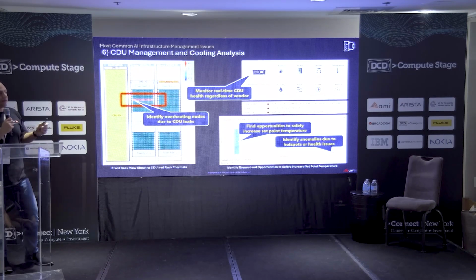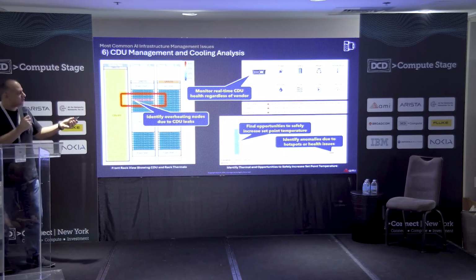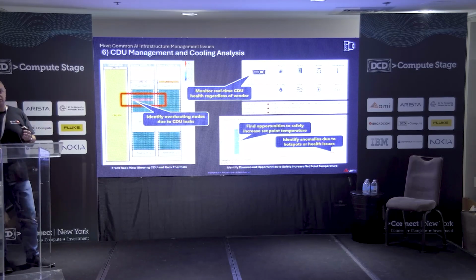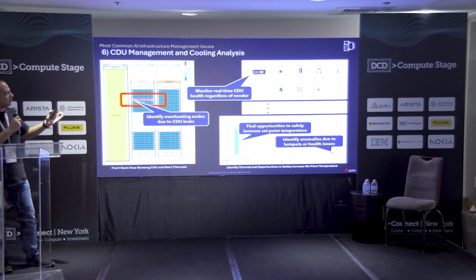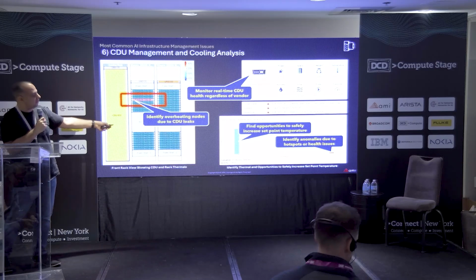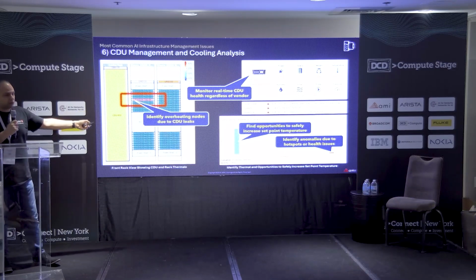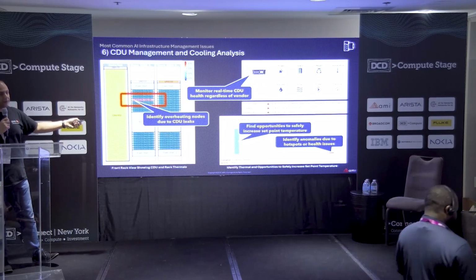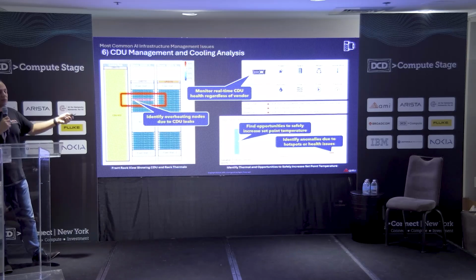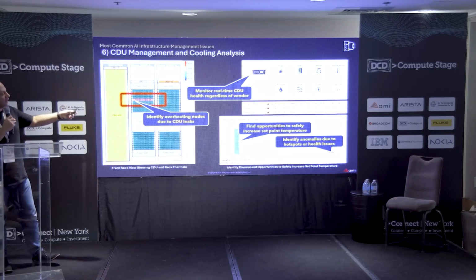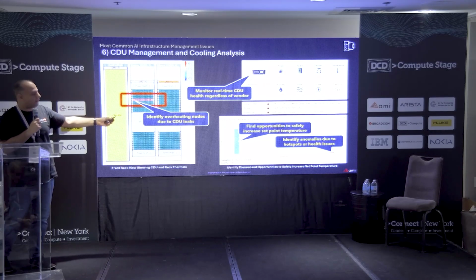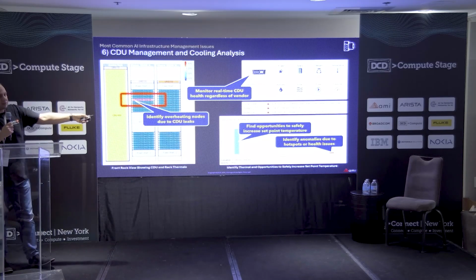Related to that is general cooling analysis. You can use DCM, using each device as a thermal sensor, to identify very quickly if you're unnecessarily overcooling your rooms. We find this happening all the time, and the amount of energy savings you can make by safely increasing the set point temperature just a few degrees is phenomenal. Again, with this same kind of graph, you can identify those hotspots that we talked about.